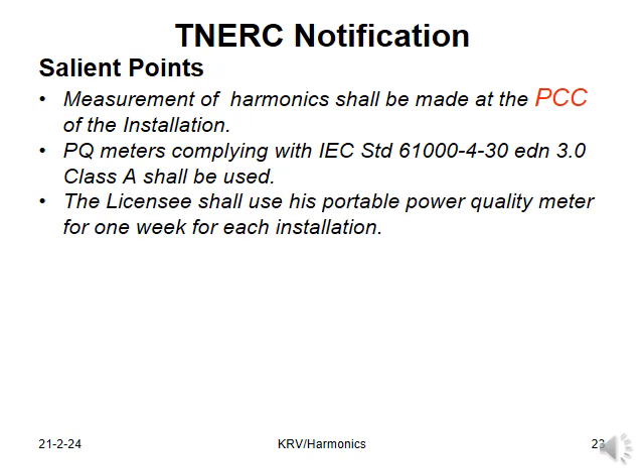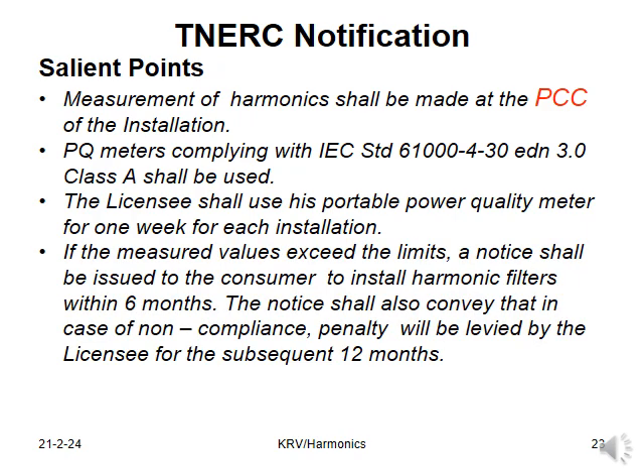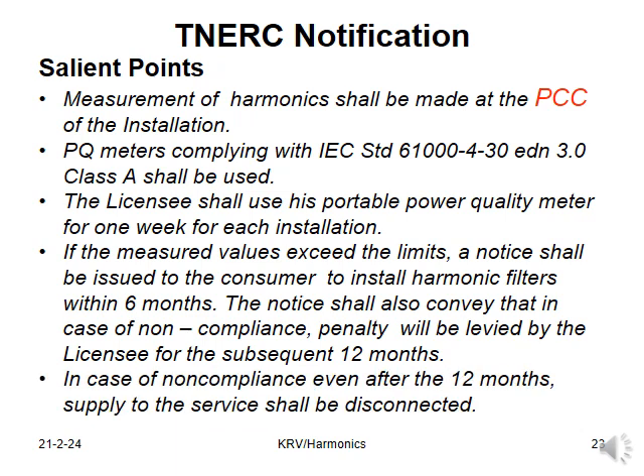The licensee shall use his portable power quality meter for 1 week for each installation. If the measured values exceed the limits, a notice shall be issued to the consumer to install harmonic filters within 6 months. The notice shall also convey that in the case of non-compliance, penalty will be levied by the licensee for the subsequent 12 months. In case of non-compliance, even after the 12 months, supply to the service shall be disconnected.